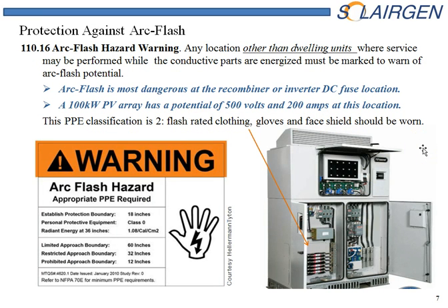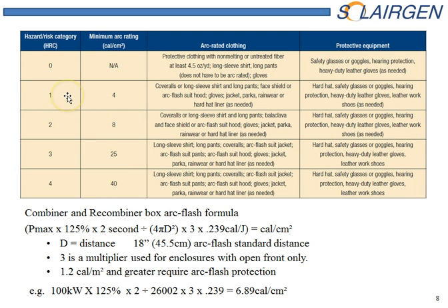Arc flash is something that occurs with high voltage and high current, so it's basically a commercial issue. If you have any location in a circuit where you can work on it live and you have direct access to touch the live parts, there must be an arc flash warning sticker on the face of the equipment, indicating the amount of heat, the calories per square centimeter, and identifying the type of clothing that is required if you get inside of this boundary where the temperature rises to the point where it could be damaging or fatal.